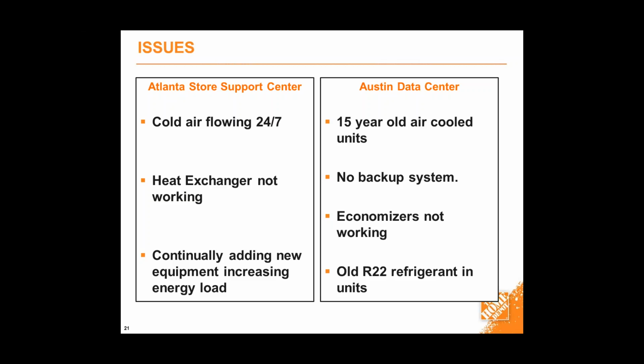In the Austin data center we had different issues. It's an older building, the units were about 15 years old and air-cooled. It's amazing to try and cool a data center with air-cooled units. We also had no backup, so anytime there was an emergency our technicians were on call 24/7 to come out and work on the system. None of the economizers on the roof were working, and all the units had old R22 refrigerant. There were times the building was so bad we had associates up on the roof with water hoses cooling it off.